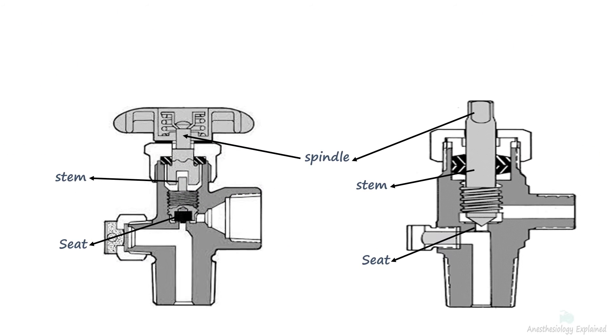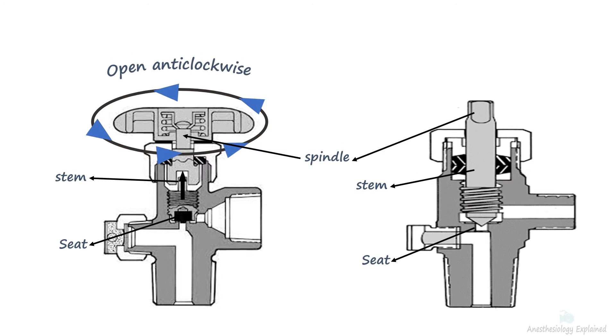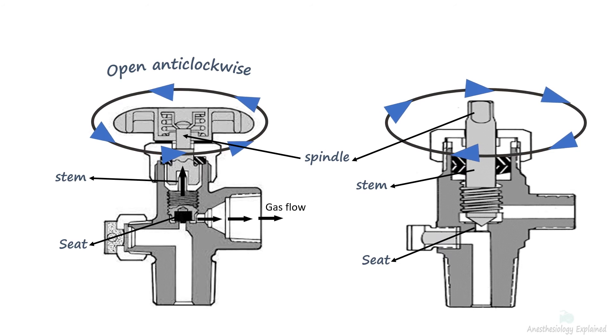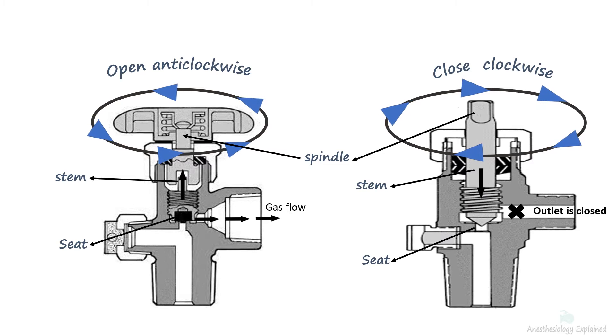To open the medical cylinder, the spindle of the stem is turned anticlockwise, causing the stem to move away from the seat, thereby allowing the gas to pass through the port. In contrast, to close the cylinder, the spindle of the stem is turned clockwise, effectively sealing it against the seat and closing the outlet. This controlled operation ensures the safe and precise regulation of gas flow from the cylinder.